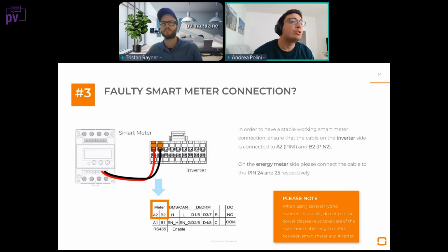And on the Chint meter in particular, connected with our three-phase hybrid inverter, we are using pin number 24 and 25 on the energy meter, 24 being RS485A and 25 being RS485B. And then we are connecting them to the same green communication connector that we have in the three-phase hybrid inverter. And this is connected to pin number 1 and pin number 2. Sorry, there is a typo here, pin number 2. So to the A2 and B2. And so these are the pins that you must use. You can see from the drawing here and also from the schematic below that A2 and B2 are where the meter is connected.